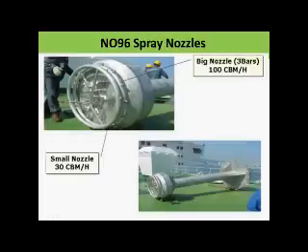Why I'm telling you, please note it down, is that this is the pressure you will be giving when you are using the simulator in NO96. Then there is a small nozzle, and you can see the nozzles are placed at a higher distance, and there is also a center nozzle. If we do not want the cooling to be very fast, we can use just the 30 cubic meter capacity small nozzle and cool down slowly and gently.